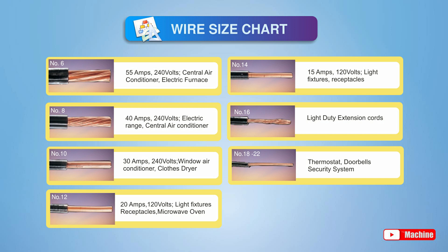The ampacities in this table are for copper wires in NM cable. The ampacity for the same wire in conduit is usually more, while the ampacity for aluminum wire is less.